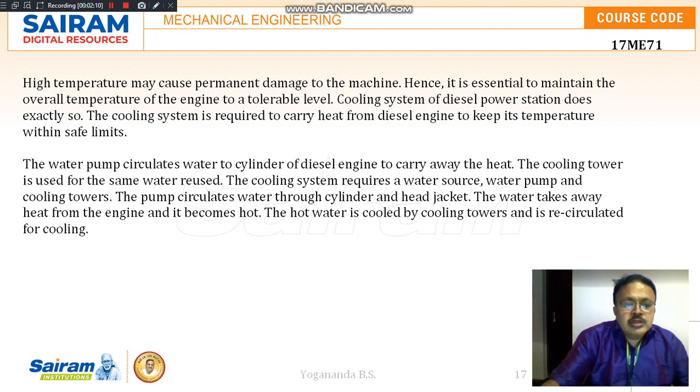The same water, which is carrying the heat, will get heated up, so the temperature of the water has to be reduced. It will be brought to the normal temperature using the water cooling towers, so the cooling system requires a water source, water pump and the cooling tower here. The water which takes the heat away from the engine will become hot. This hot water, as I said, is cooled by the cooling towers and will be recirculated for cooling.